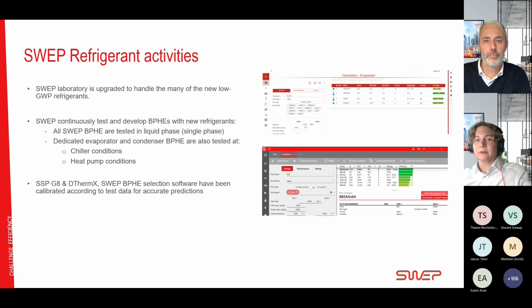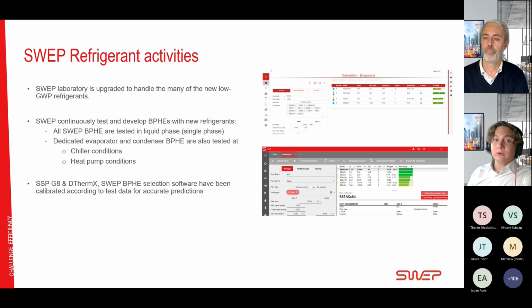So we have a standardized thermal and hydraulic test that everything will go through. And we do this to ensure that we have a good performance model to build up. But then we also want to ensure that we can fine-tune the accuracy even more with new refrigerants. And we do that by doing standard chiller and heat pump tests. So we do that at standardized conditions for these applications. So we take the evaporator and condenser tests with different refrigerants, we take the data from those, and ultimately we will use the data to calibrate the models we have in our selection softwares.